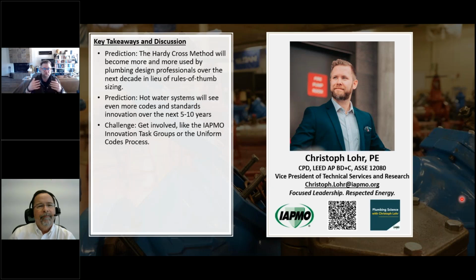So if you have a system that has 50, 100 balancing valves, you're talking about probably days, if not weeks worth of effort trying to get that system balanced, as opposed to an automatically balanced system that's predominantly made up of automatic balancing valves, where the valves are doing that work for you. And that's really a lot of the guidance in that ASPE Legionella Design Guide, which pointed to that difference. Yeah, the advantage of the manual balancing valves is that they're adjustable. The disadvantage is they're adjustable, and you have to adjust them in order to get them to work right. And that should be a consideration as part of the design.